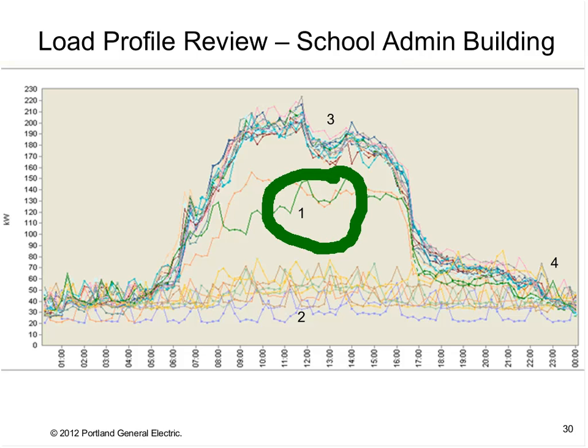Number 2, down at the bottom, you'll see a lot of cycling going on. This would raise my attention to something shutting on and off and probably being very costly. We had an example of this a few years back where another school got their bill and noticed it was very high when it should have been, you know, next to nothing.